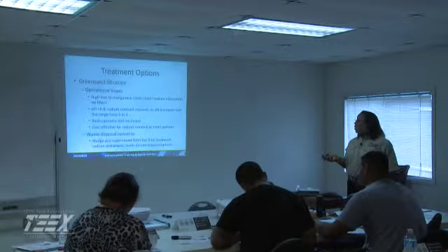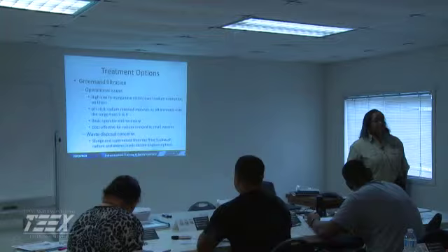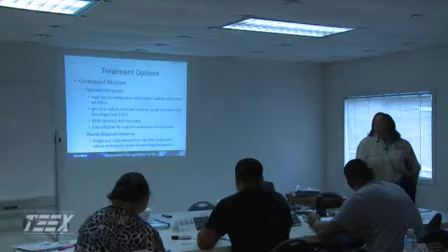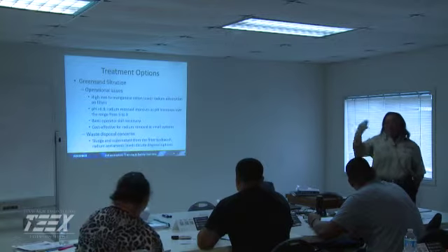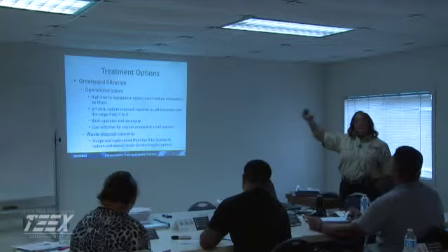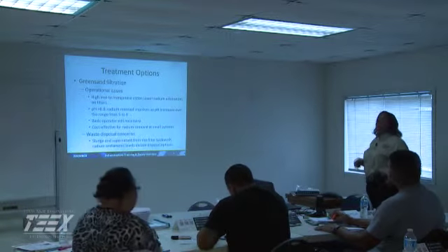Okay, pH greater than 6.8. Radium removal improves as pH increases, but as you know, for the most part, how do we operate most of our plants? At what pH range? 5 to 7? You drop as low as 5? No, 6.5 to 7.5. Okay, yeah, more around neutral. So in some of these situations, you may have to add chemicals to raise the pH to get to the optimum level for it to be effective. In other instances, you may have to add chemicals to lower it. And we'll see that with the membrane technology too.